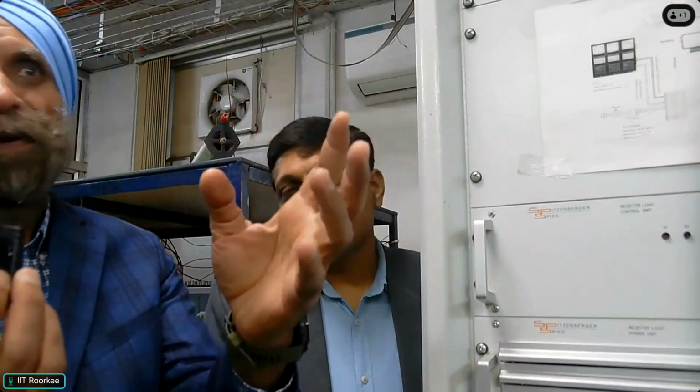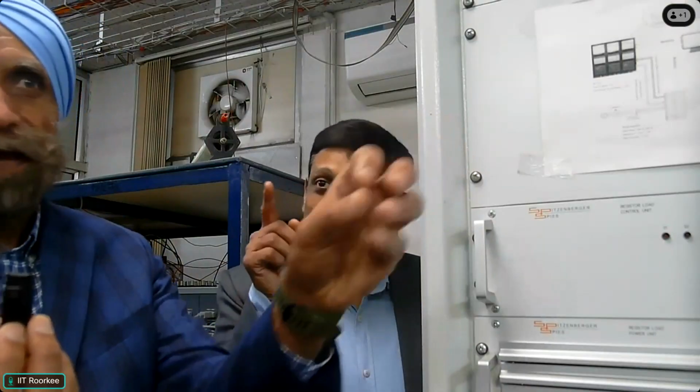So you have to give it an analog signal, and inside it converts to digital signals and does the phasor calculations and so on. Whereas with a merging unit, you can separate that out. The role of merging units is to take analog data, sample it and give you the digital numbers. Okay, we will go to that side now.